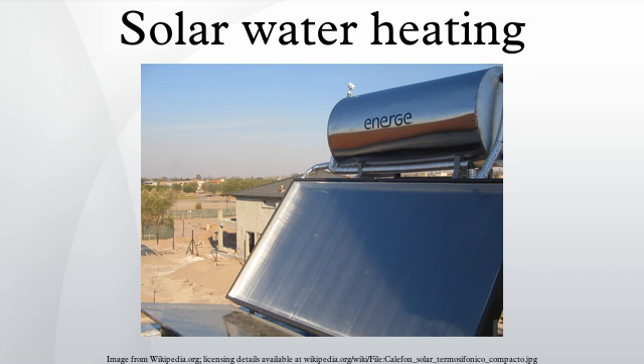An active solar water heating system can be equipped with a bubble pump instead of an electric pump. A bubble pump circulates the heat transfer fluid between collector and storage tank using solar power, without any external energy source, and is suitable for flat panel as well as vacuum tube systems. In a bubble pump system, the closed HTF circuit is under reduced pressure, which causes the liquid to boil at low temperature as it is heated by the sun.